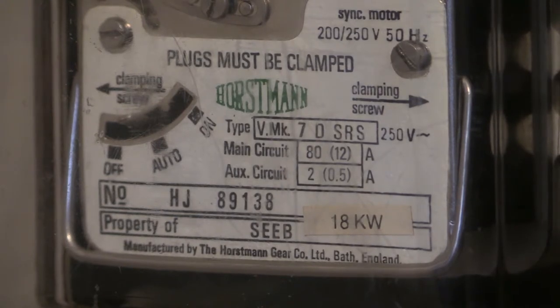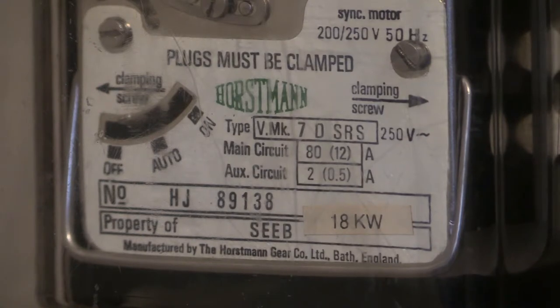It can also be seen that the capacities for the time switch are detailed on the specification plate where it says main circuit 80 amps and auxiliary circuit is 2 amps. I have reason to believe that the numbering in brackets for each contact is the inductive load, so it'll be 12 amp inductive for the main circuit and half an amp inductive for auxiliary circuits. Also on the specification plate you can see a little lever sticking through where it says off, auto, and on. That is a manual option, but these time switches are installed by electricity boards and are sealed and are not accessible to the electricity user.